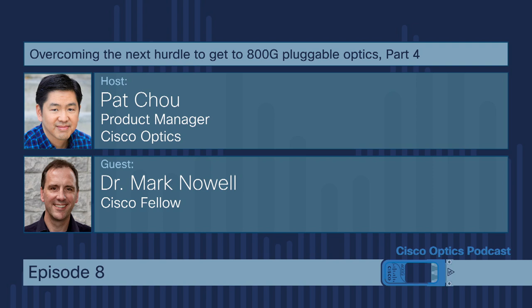It's definitely easier on the cooling of the optics to have it being drawn in, having the cold air from outside hitting the optics first, because we then have to cool whatever's behind the optics, and we generally have a very high power ASIC back there as well. So the thermal design of the systems is very complex.